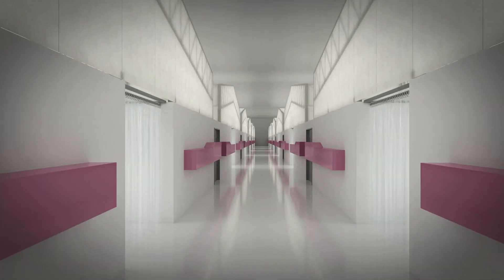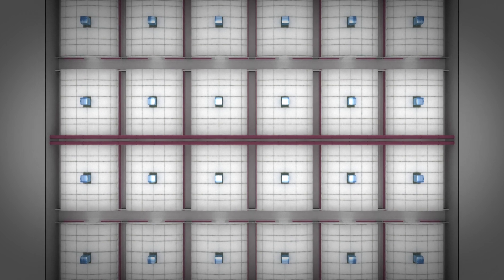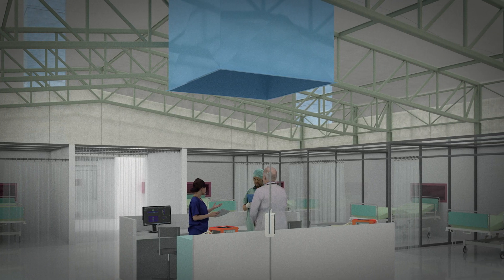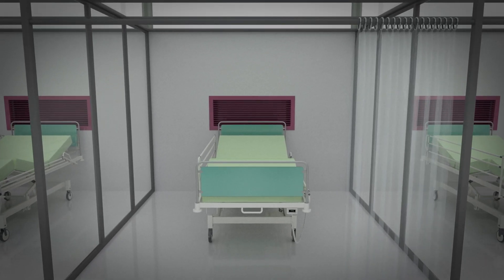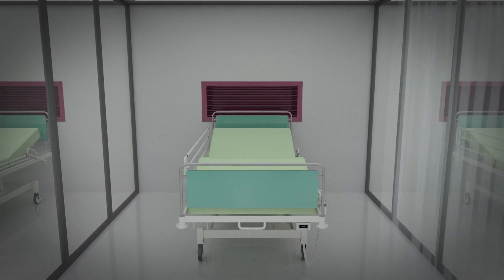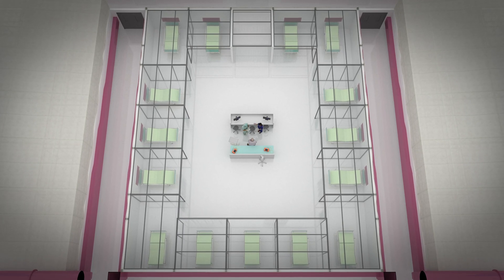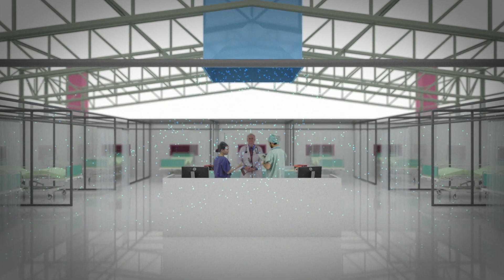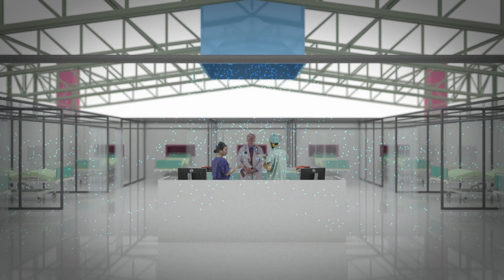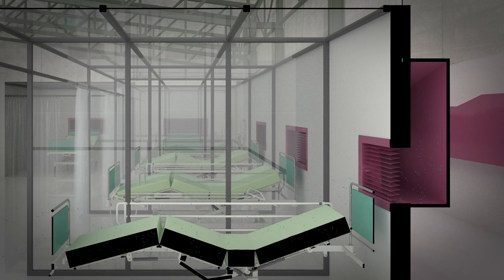The first makeshift hospital in India uses the underlying principles of this scheme. It inserts a dense layout of sealed square wards of 15 beds apiece in impervious tents, with stub partitions between each bed to head height, and ideally a fold-away polythene sheet to head height to limit further leakage of virus-borne exhaust air into the ward. A central nurse station and dock for ventilators, with a natural or fan-assisted supply of fresh air from the rooftop, preferably via a filter, dropping into the central zone for staff. Air is exhausted mechanically at each bed head, safely to the exterior.